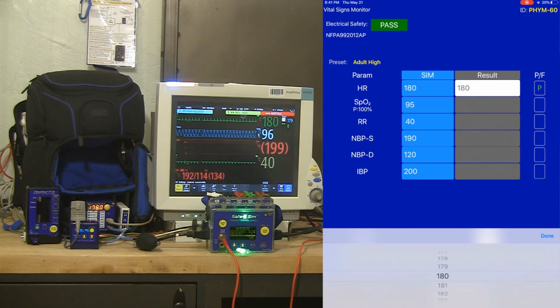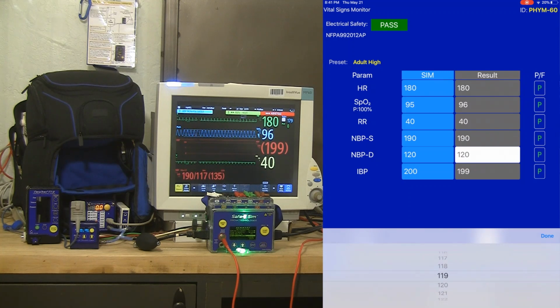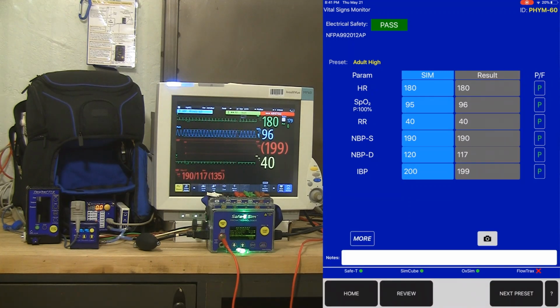That's a pass. My SpO2, target is 95, result is 96. My resp rate, target is 40, result is 40. Invasive pressure, 199. All of those parameters, as soon as we got on the screen, were immediately set on the test equipment because of that Bluetooth connectivity. I've got an NIBP reading now of 190/117, so I'm going to tap that in, and I'm good to go. All of those parameters are tested and passed.